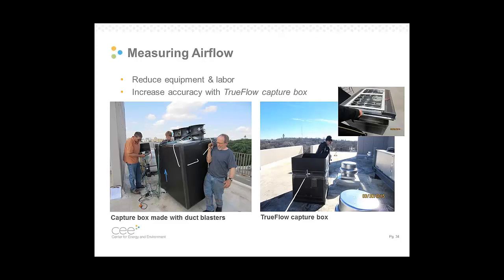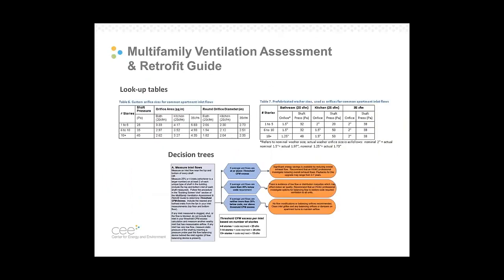By the end of it, Jim Fitzgerald landed on this prototype, which uses the Energy Conservatory's TrueFlow meter. This is a meter that just uses the DG700 gauge. There's no power required, it's lighter weight, and one person can operate and move this box around. So you get a flow measurement that's more accurate with lower cost equipment, in minutes rather than hours. This was a really great improvement in efficiency for measuring airflows.